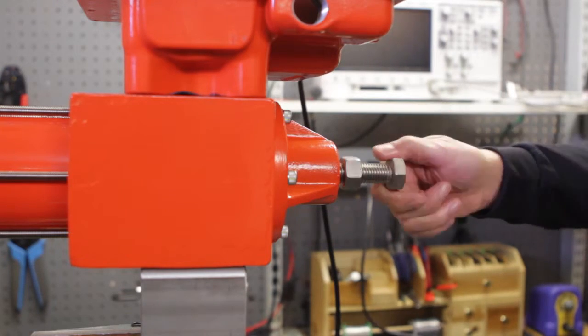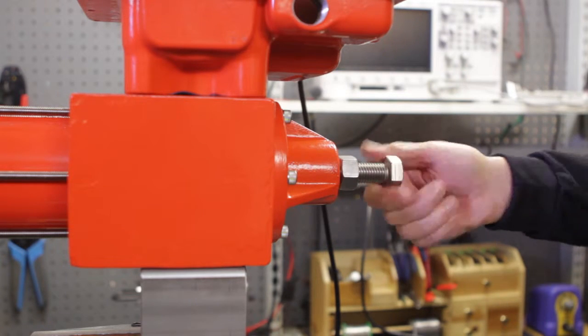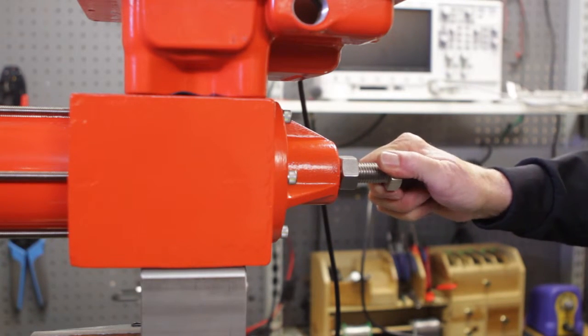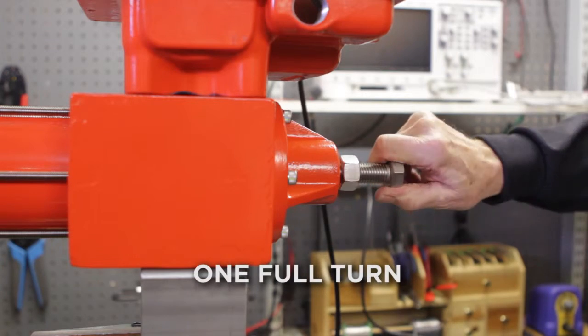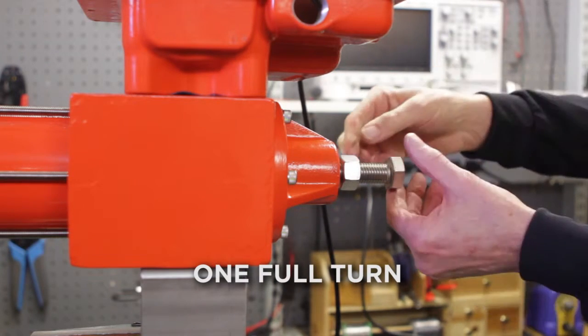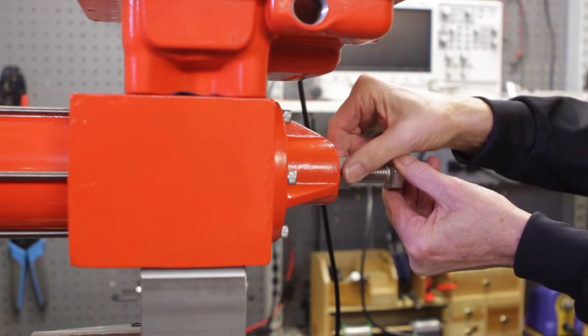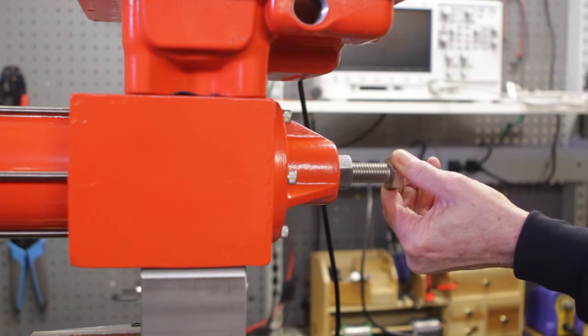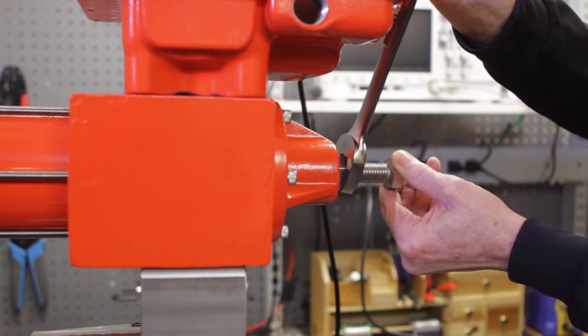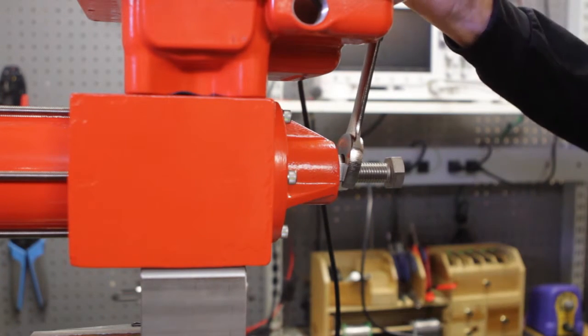With the power on, rotate the mechanical stop screw clockwise until it stops, and then back it out one full turn. Hold the screw so it does not move, and using the 1-1/8 inch open end wrench, tighten the jam nut.